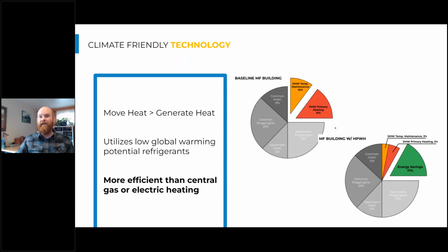But luckily with the heat pump water heater, if we apply it correctly, we both address that primary heating load and the temperature maintenance heating load, and are able to save that 17% of the annual energy. So a great reason, and once again, this is one system, typically your water heating system, that's in a basement or rooftop mechanical space, whereas some of our other systems, like our plugs and lights, are distributed all across the building. So it's a great opportunity here for us to focus in and really address that system efficiently, while also addressing other energy usages in the building as well.